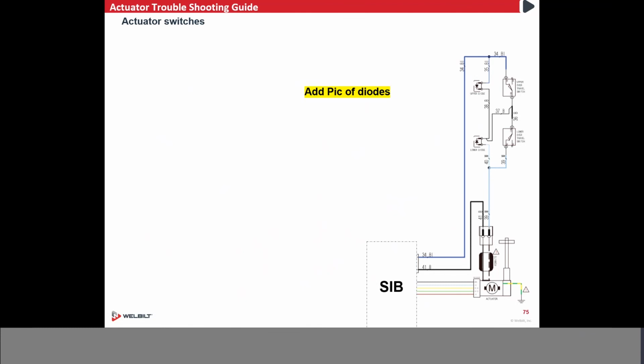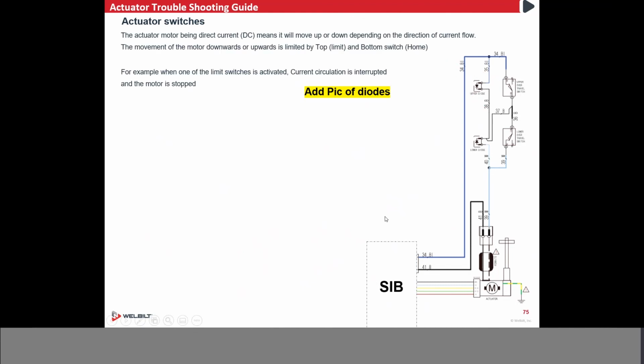its target. For an example, let's say it's coming up to the upper home switch, but it never sees it. It hits the over travel switch, removes the power from the motor, and after 40 seconds, it gives you an error 6. Same thing on all the other grills. And when you get an error 6, it says push green button to try again.